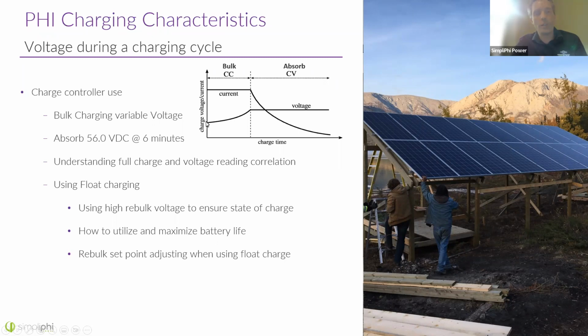That low voltage is going to charge, let's suppose we just have one battery, at 37.5 amps. So that's going to be a constant current. If you look at the top graph here, it's of current, and current is going to be constant. How long is it constant? Well, until it hits the absorb setting in the inverter. And so the bulk charging cycle consists of this constant current process.